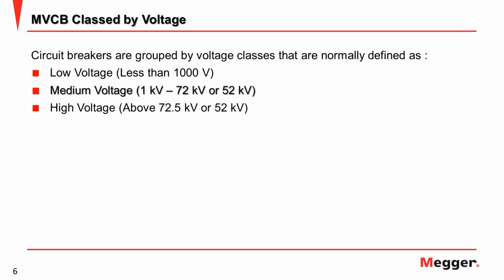LV, or low voltage circuit breaker, is for voltage less than 1 kV. And for medium voltage, there is a lot of literature on this. Some literature sets 1 kV up to 52 kV, and in other literature you can find up to 72 kV. But mostly in the world so far, I find maybe up to 36 kV for medium voltage, though above 36 kV is also considered a medium voltage circuit breaker. And above the medium voltage level, we consider it high voltage circuit breaker.